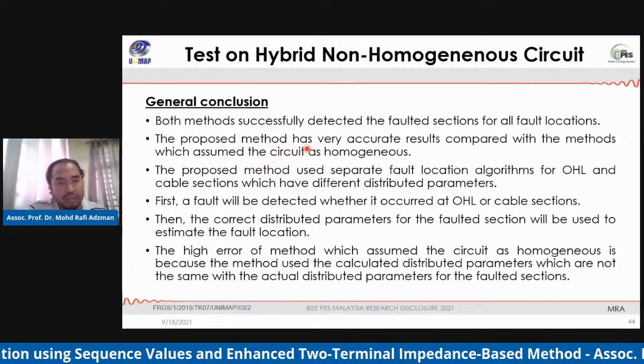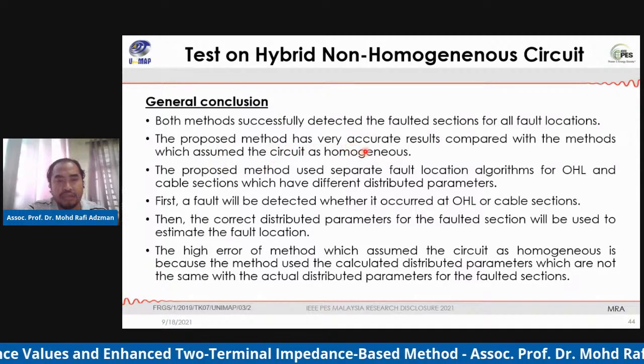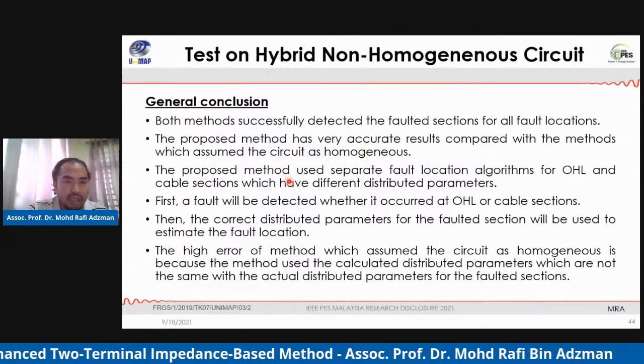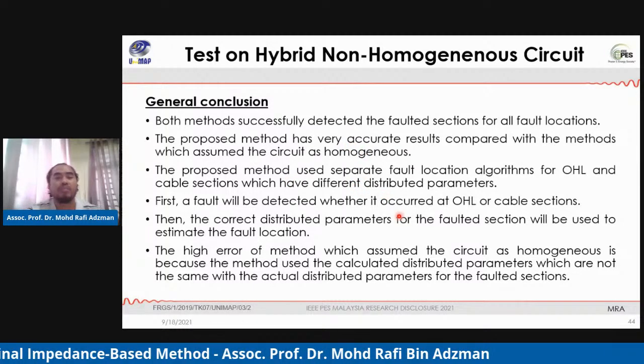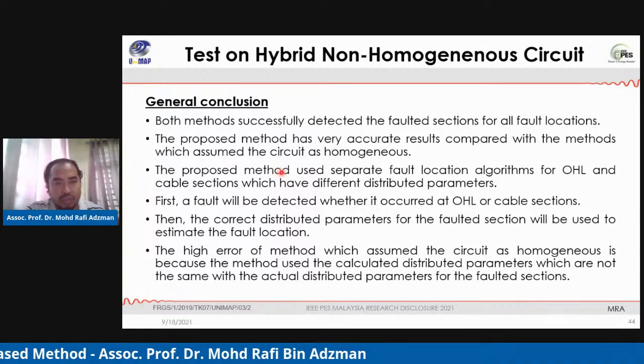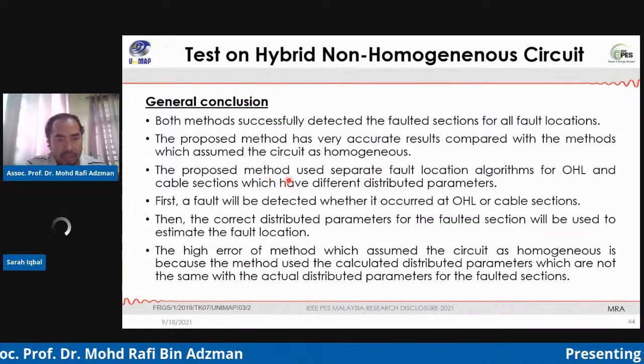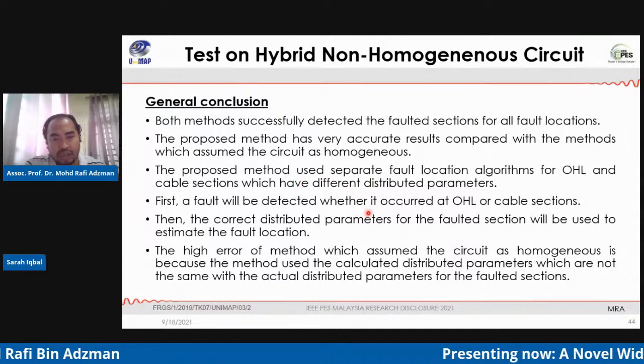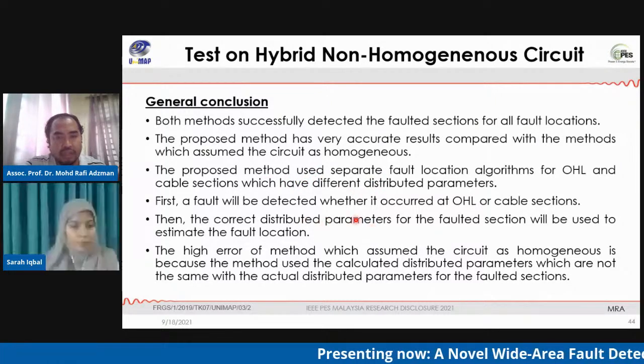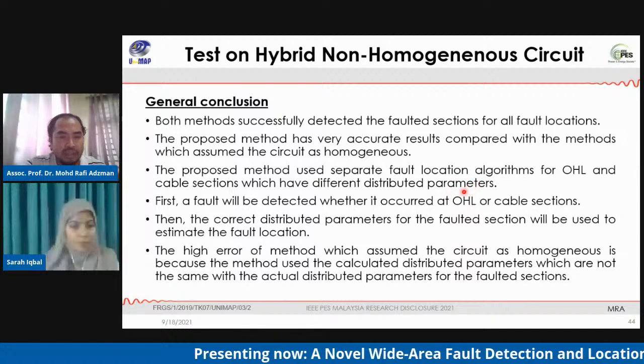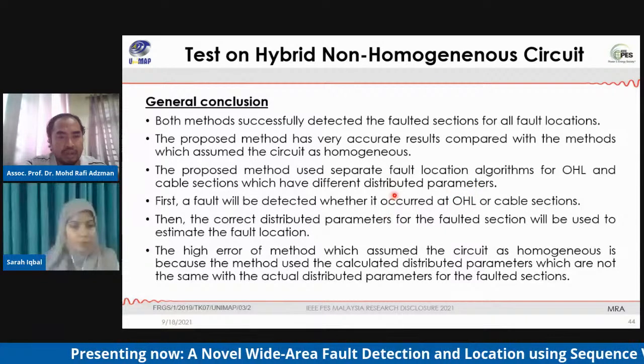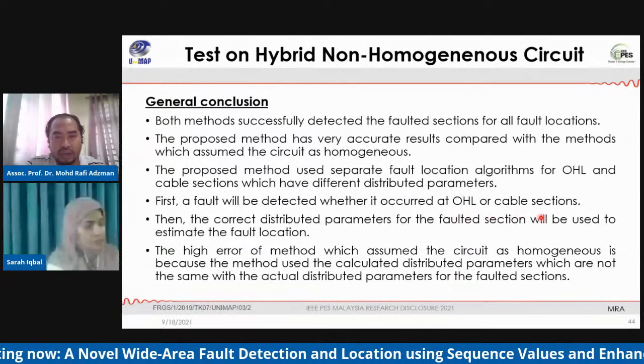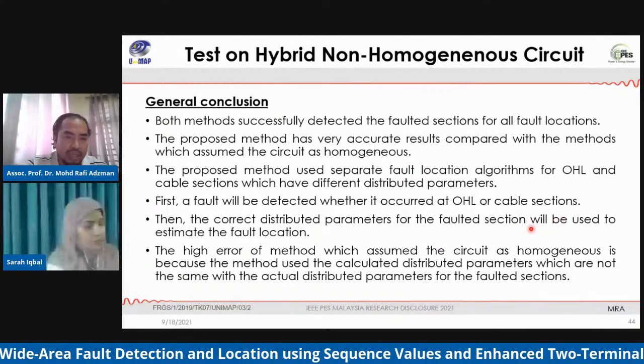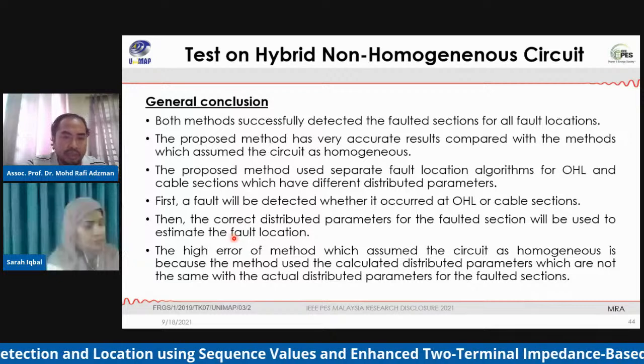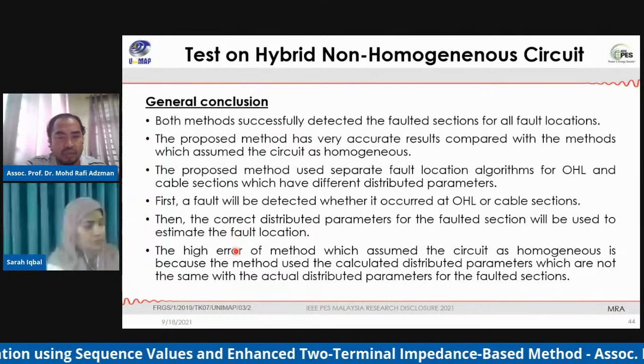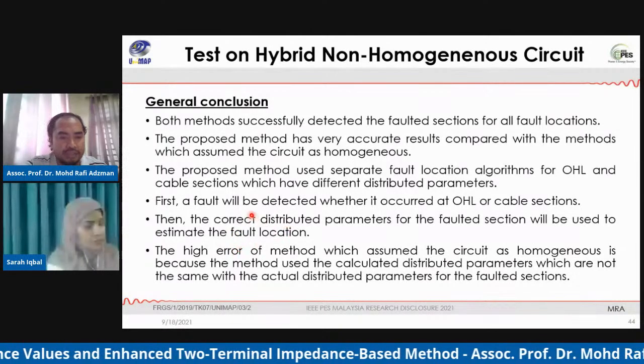Both methods successfully detected the fault section for all fault locations, and the proposed method has a very accurate result compared with the methods which assume the circuit as homogeneous. The proposed method uses a separate fault location algorithm for overhead lines and cable sections, which have different distributed parameters. First, it detects whether the fault occurs at the overhead lines or the cable section. Then the correct distributed parameter for the fault section will be used to estimate the fault location.